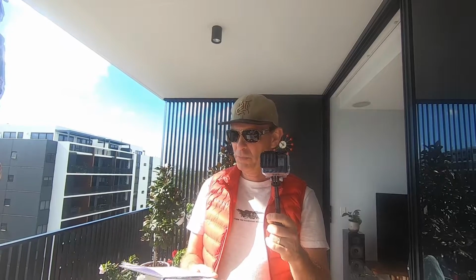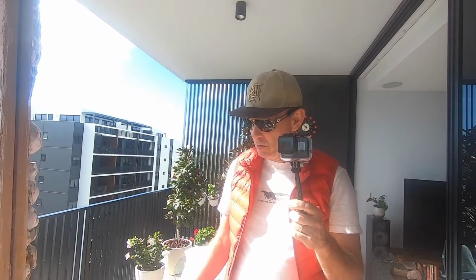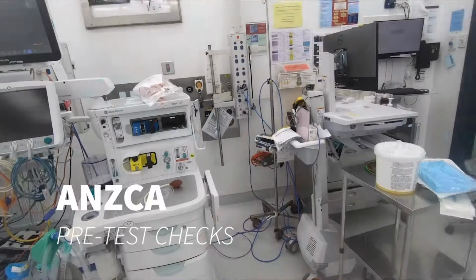And then you can generate a high pressure alarm, of course, when the machine is delivering, and you can disconnect the patient Y to see if you get an apnea, low pressure alarm. Yeah, and basically that's your level 2 test on the AISYS CS2. And of course you finish off with the emergency equipment, emergency drugs, and your syringe drivers and all the other bits. Alright, I'll make a proper version once we have the machine installed. Thank you.